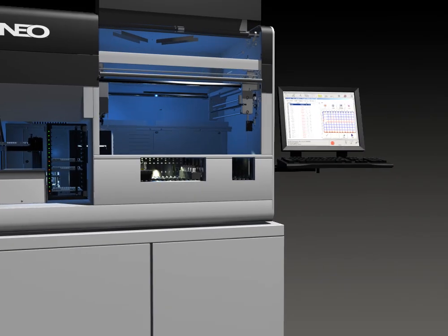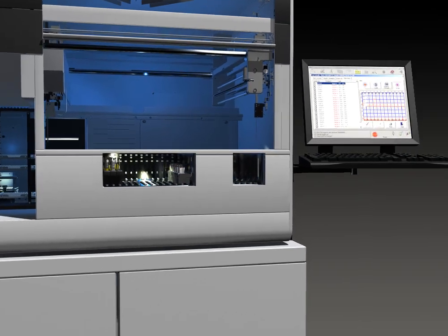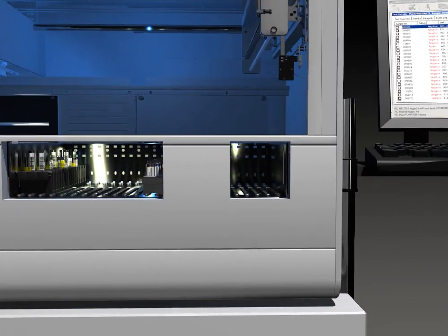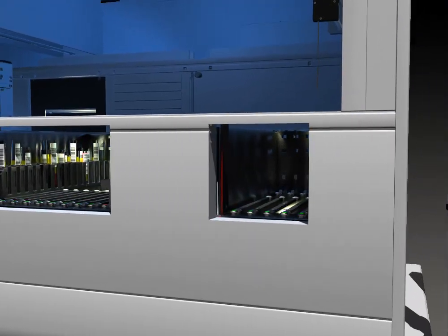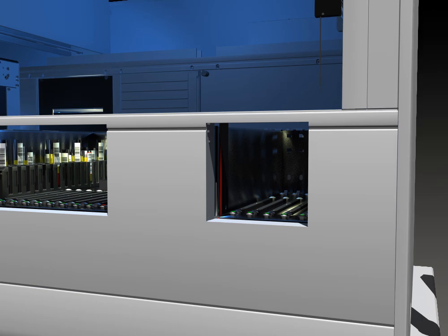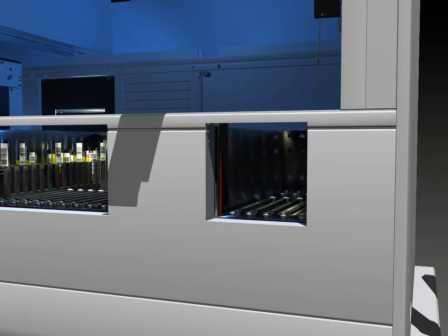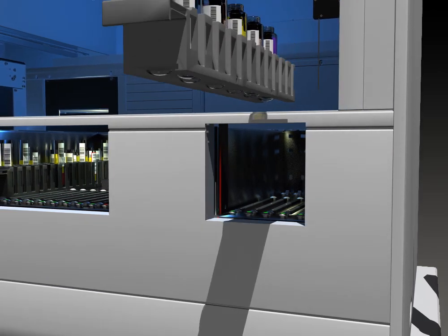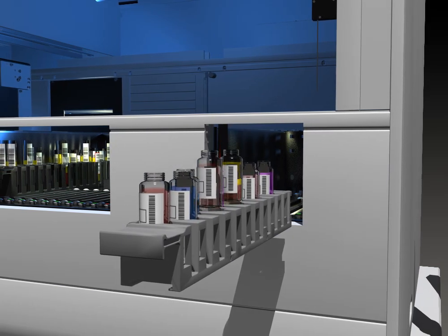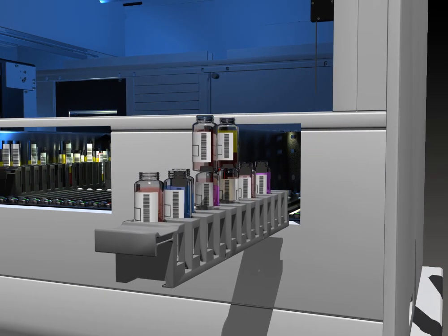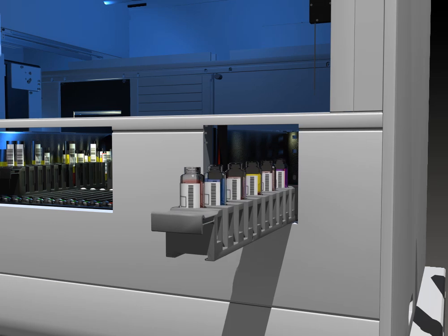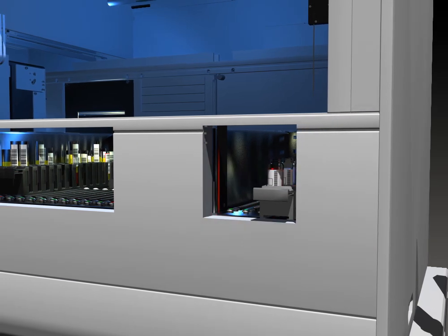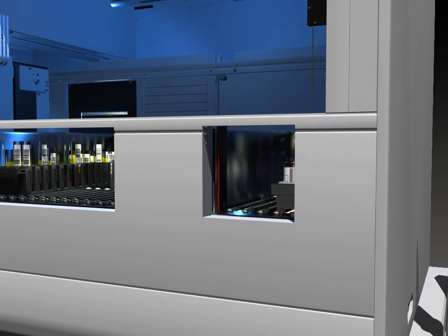In the front of the Neo, you can see the reagent and sample loading bays. Using linear racks which hold up to 16 samples each, Neo has the capacity to load up to 224 samples at one time. By using linear racks, the operator has continuous access to loading and unloading samples. The linear rack contains positional barcodes, which the Neo reads in tandem with the sample and reagent barcodes.